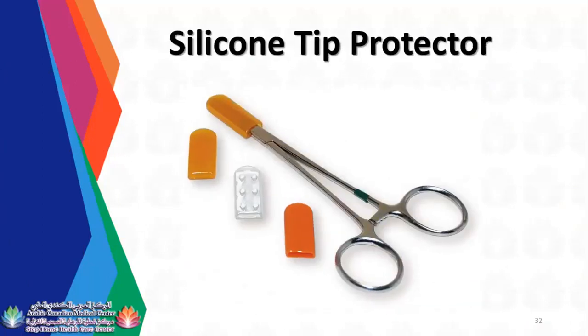For silicone tip protector, this is your silicone tip protector. Whatever edges or sharp edges, you need to put a silicone tip protector. This silicone tip protector can withstand a certain number of sterilization processes, but you need to check how many times you can reuse it.